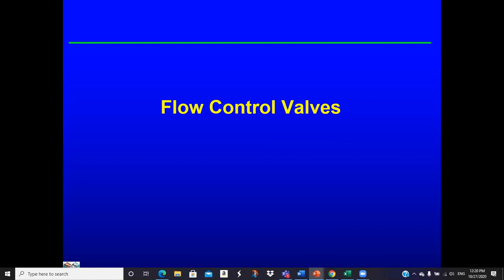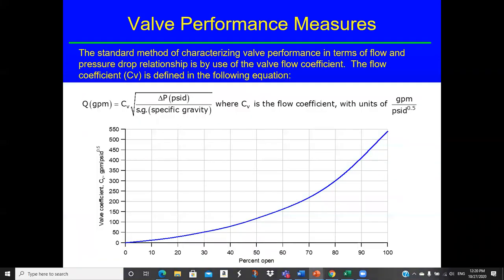Okay, let's talk a little bit about flow control valves. Shifting the discussion a little bit. This is a typical curve for a particular valve. I don't think it says on here what the valve is, but you can get these from the valve manufacturers. And so this CV is the valve coefficient, the valve flow coefficient, the C sub V.